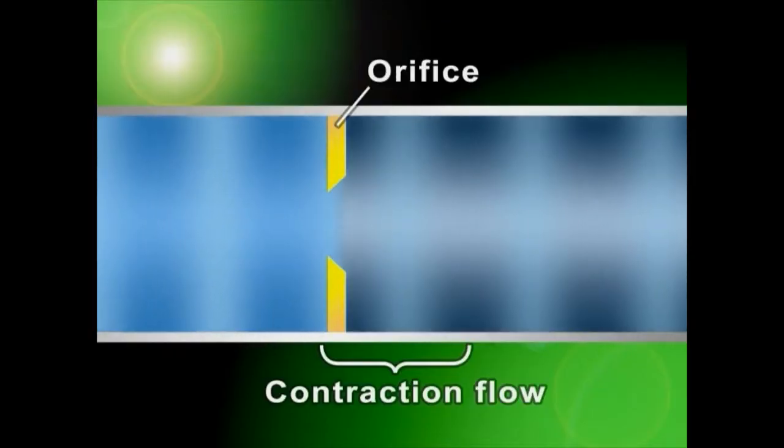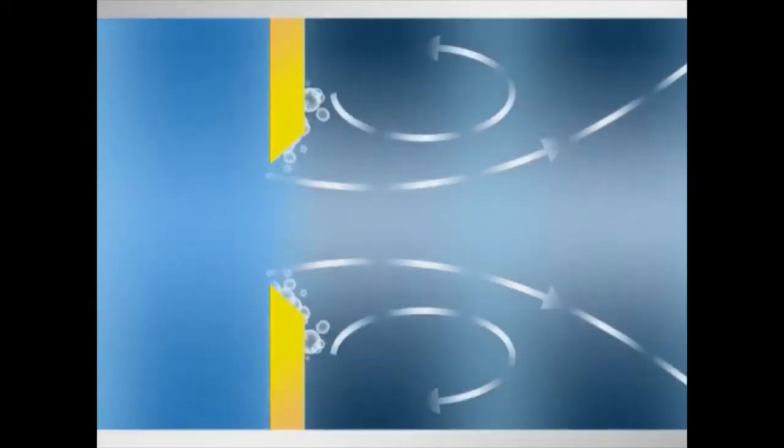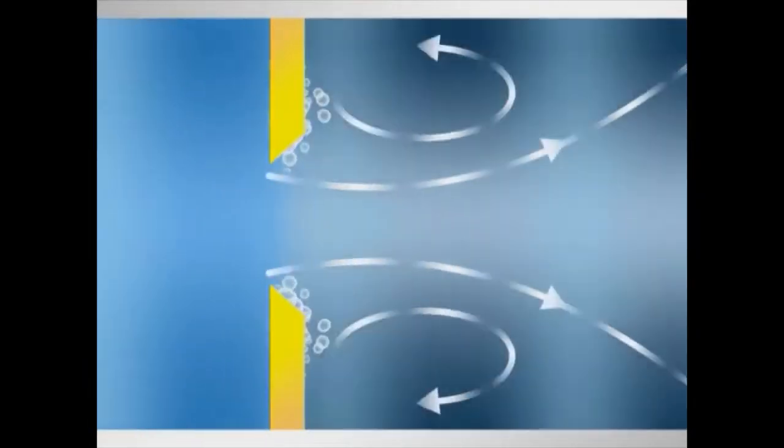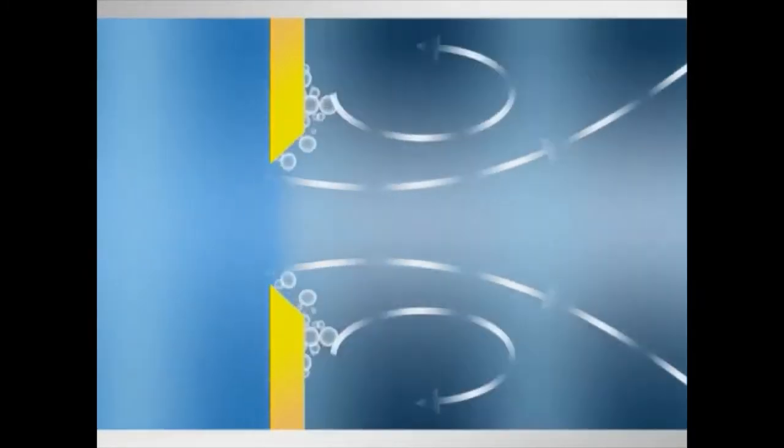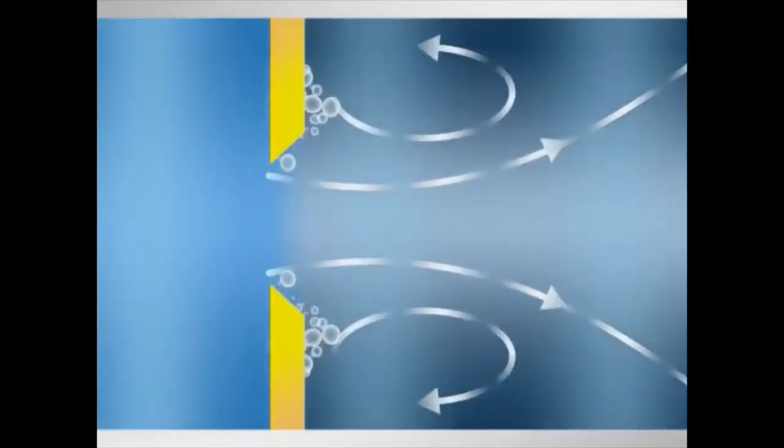When water flows fast through a region, the pressure falls below the water's vapor pressure, causing vapor bubbles to form. As they collect, these vapor bubbles create a cavity, a phenomenon known as cavitation. When these bubbles break, they produce minute vibrations that cause abrasion. Repetition of such vibrations leads to damage to parts of the pump.